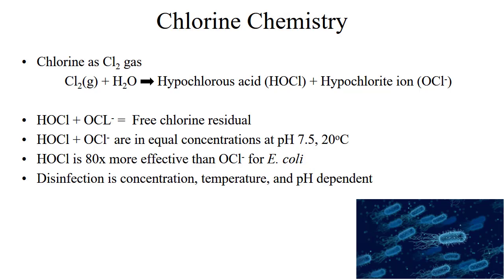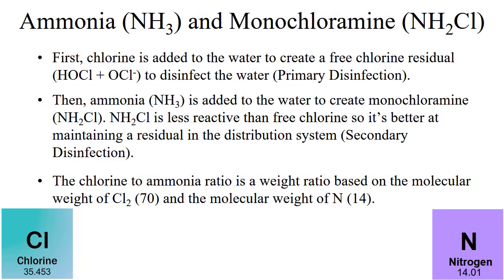Before ammonia is fed, the water is disinfected with free chlorine. This is primary disinfection, and its purpose is to remove pathogenic or disease-causing organisms from the water. Then ammonia is added to create a secondary disinfectant, monochloramine. Monochloramine is not as reactive as free chlorine, meaning it is more stable and lasts longer. Therefore, it's better than free chlorine for maintaining a disinfectant concentration, or residual, in the distribution system.